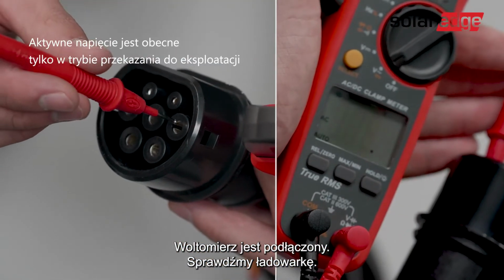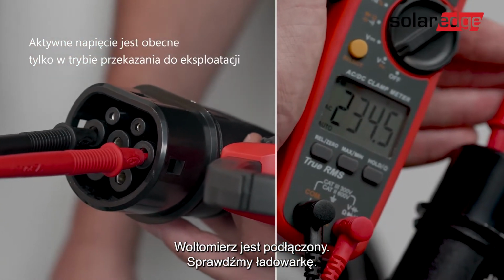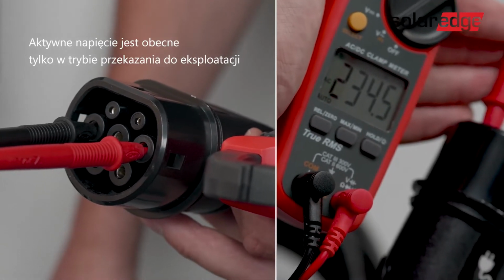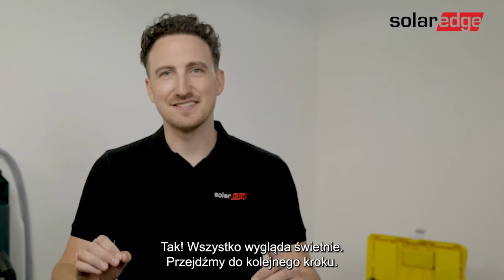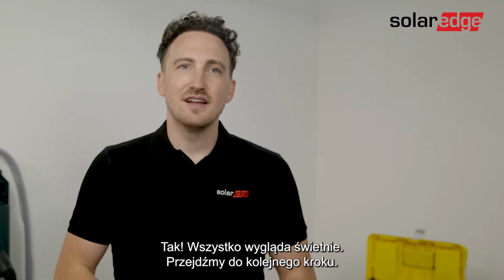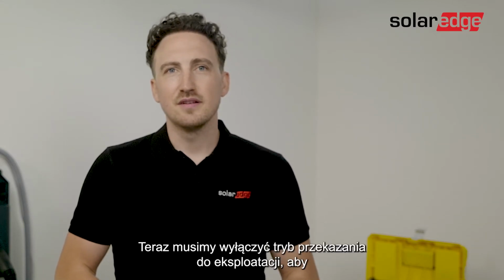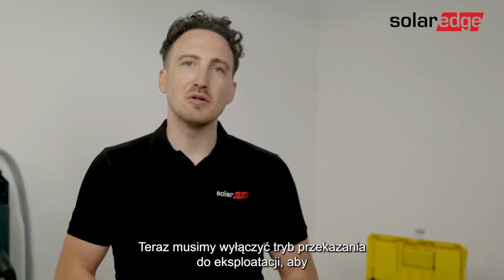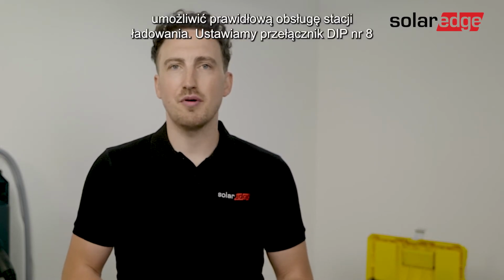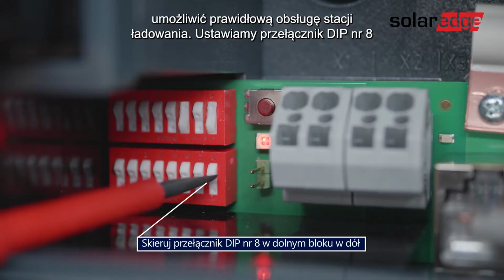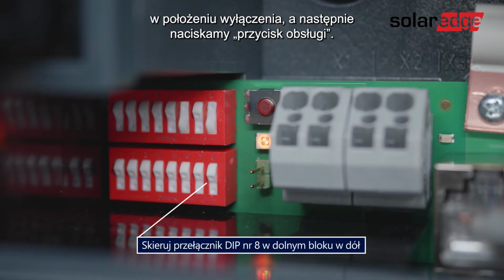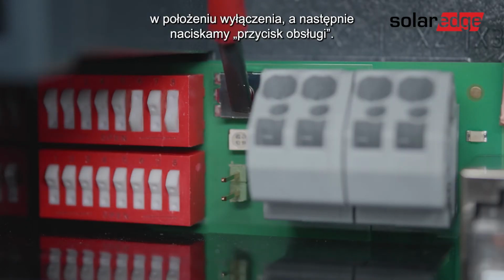Okay, voltage meter is connected. Let's test our EV charger. Yes, everything looks great. Let's move on to the next step. Now we'll need to deactivate the commissioning mode in order to operate the charge station properly. Let's set the dip switch 8 back into the off position, and now we're going to press the service button.